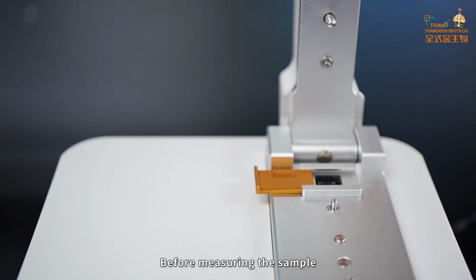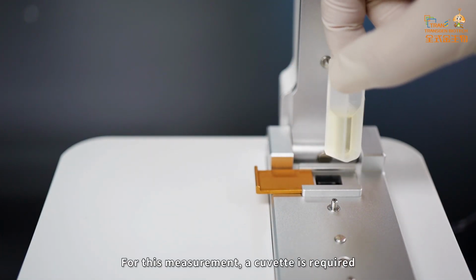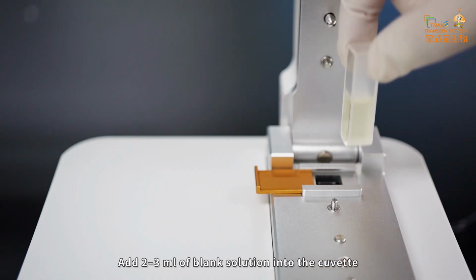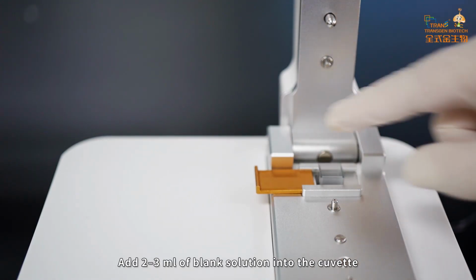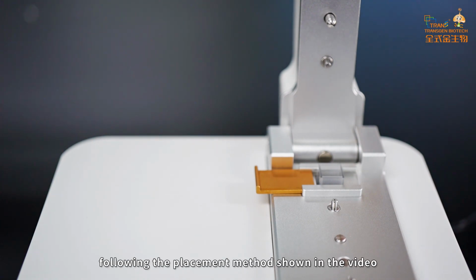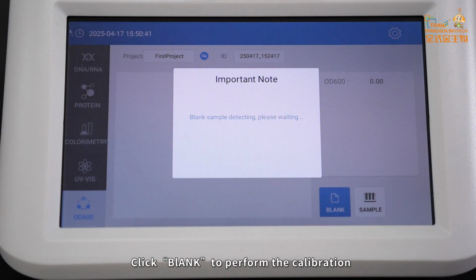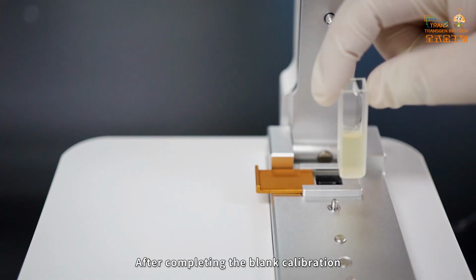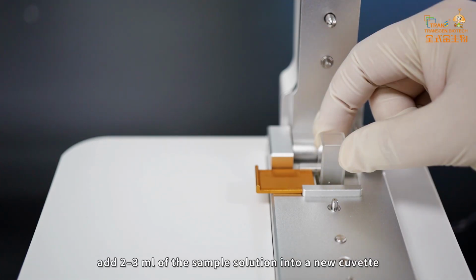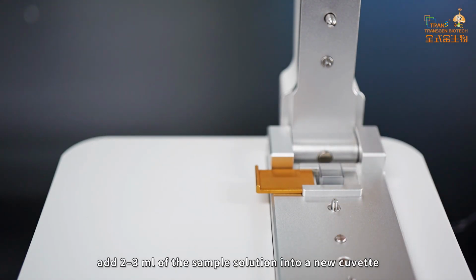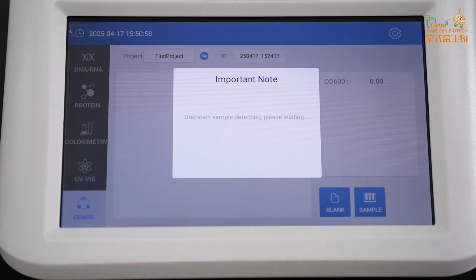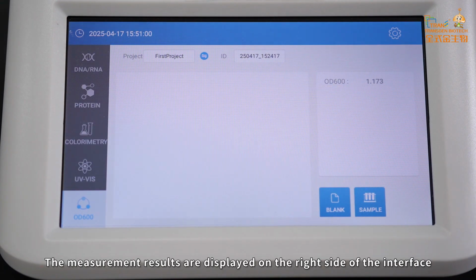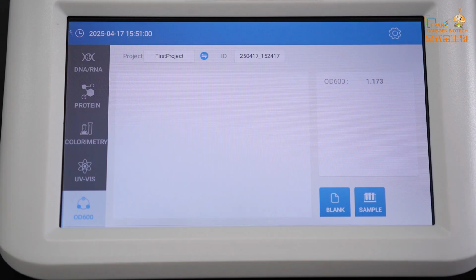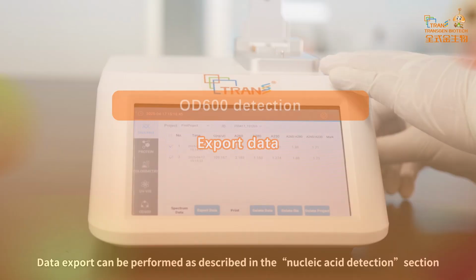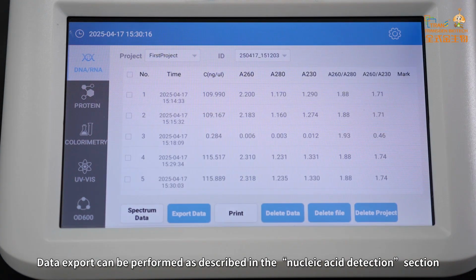Before measuring the sample, a blank calibration should be performed. For this measurement, a cuvette is required. Add 2 to 3 milliliters of blank solution into the cuvette, following the placement method shown in the video. Click blank to perform the calibration. After completing the blank calibration, add 2 to 3 milliliters of the sample solution into a new cuvette and place it into the measurement chamber. Click Sample to start the measurement. The measurement results are displayed on the right side of the interface. Data export can be performed as described in the nucleic acid detection section.